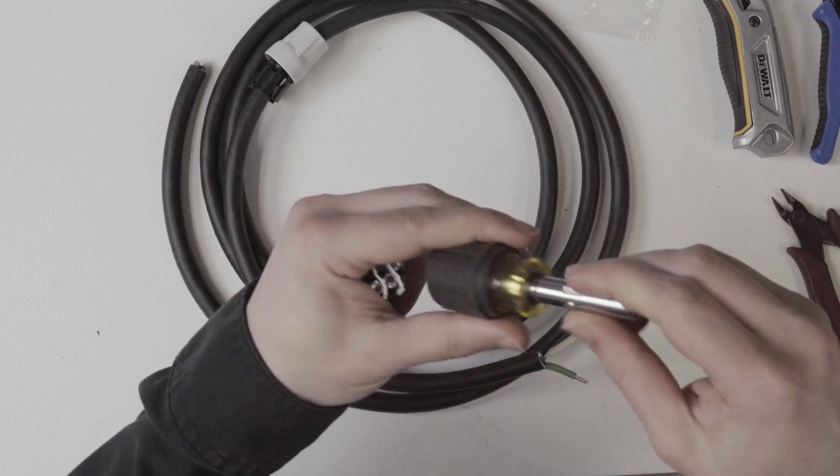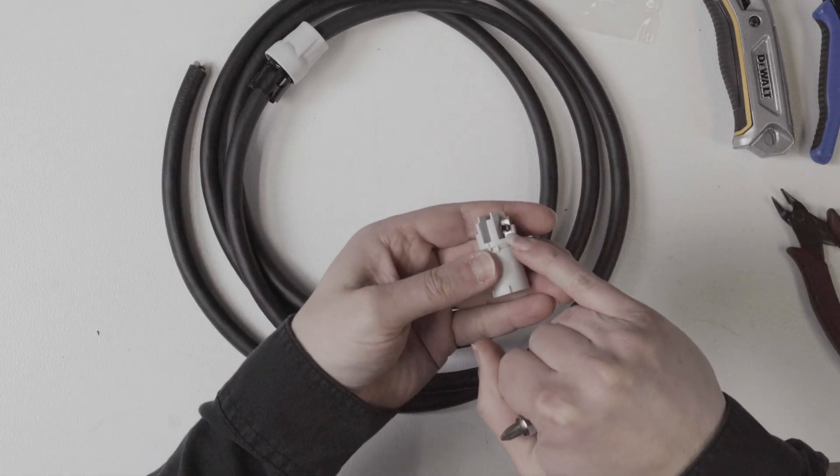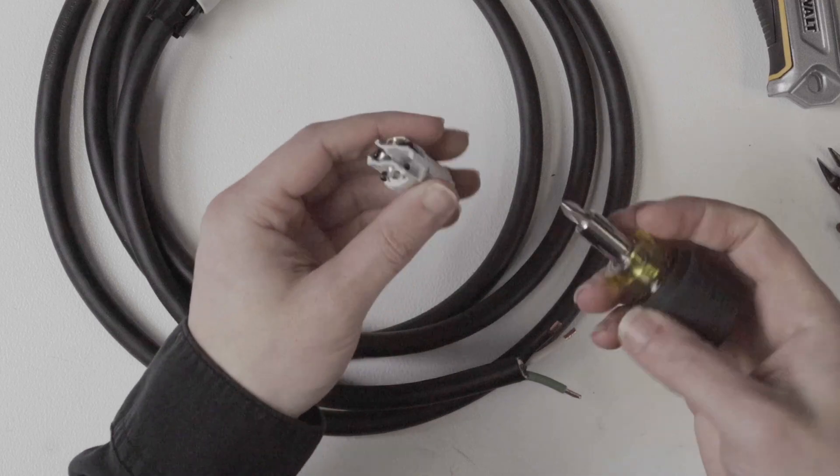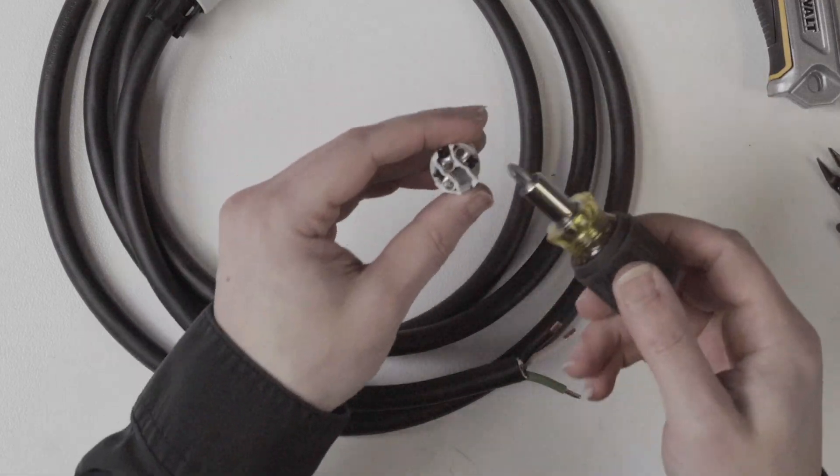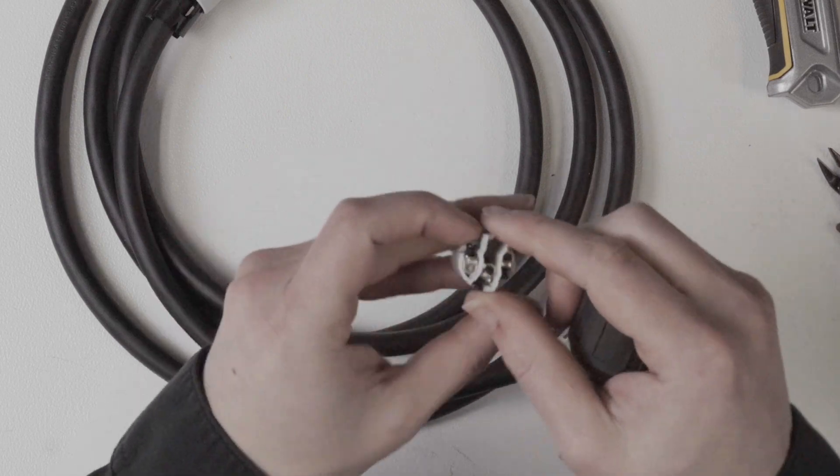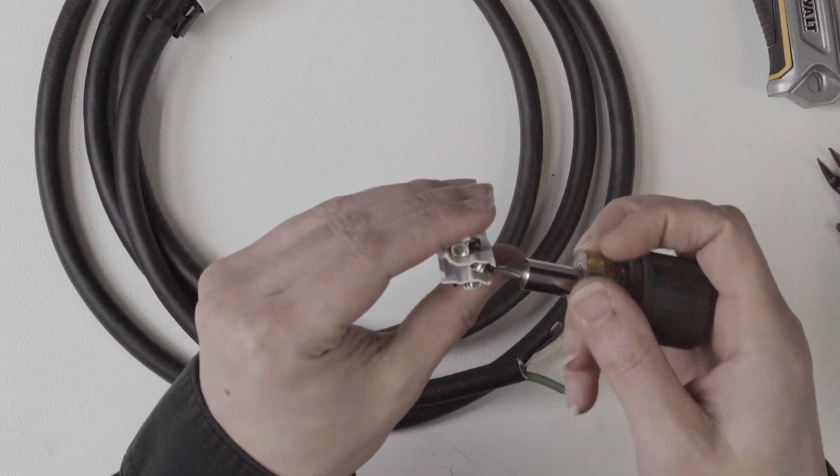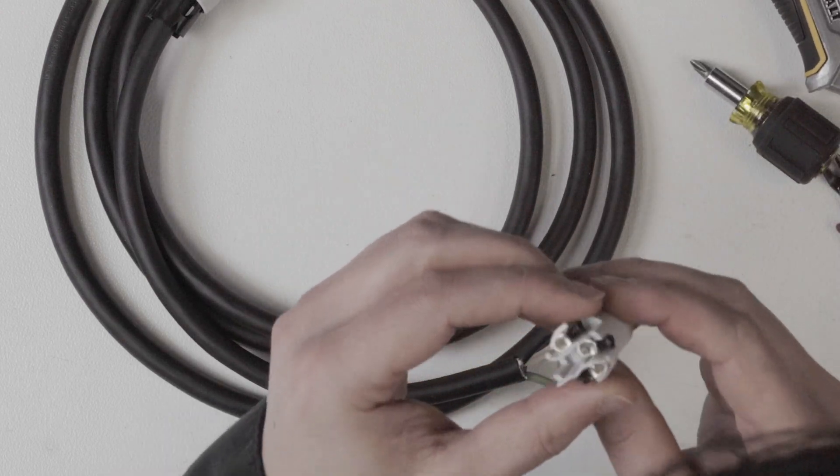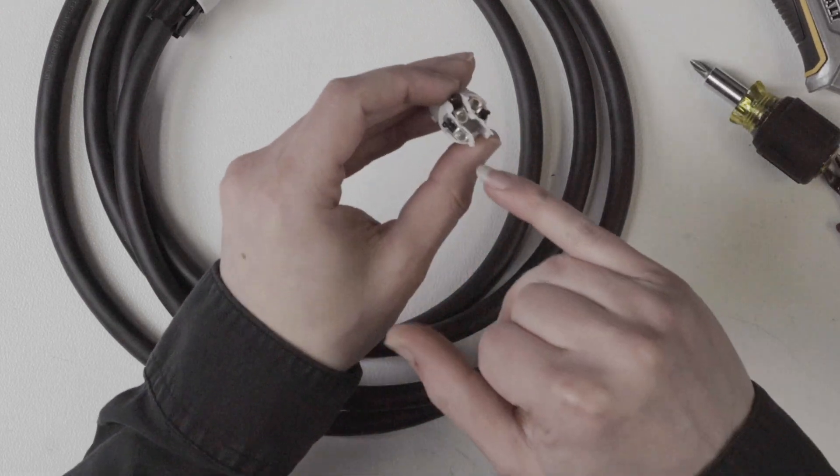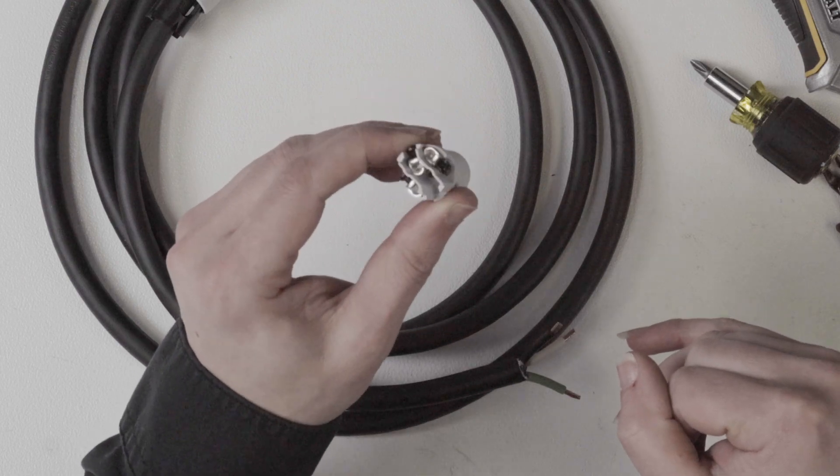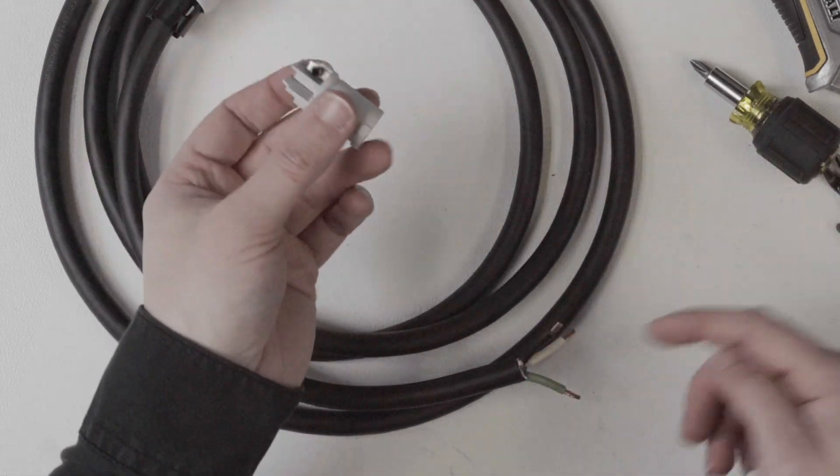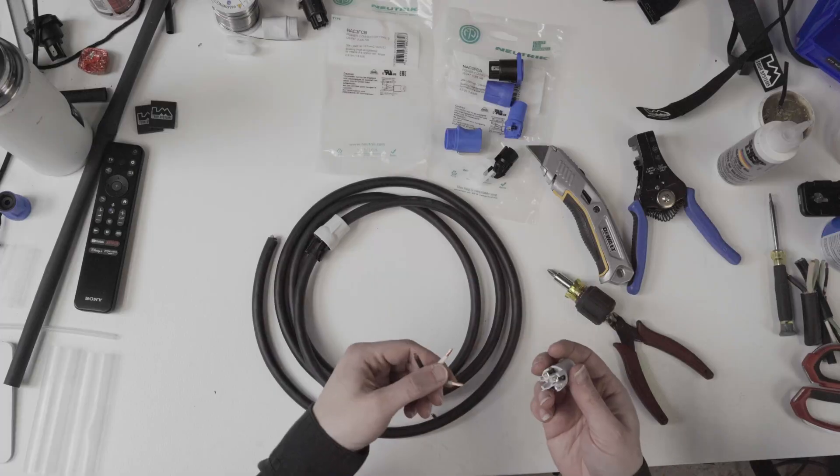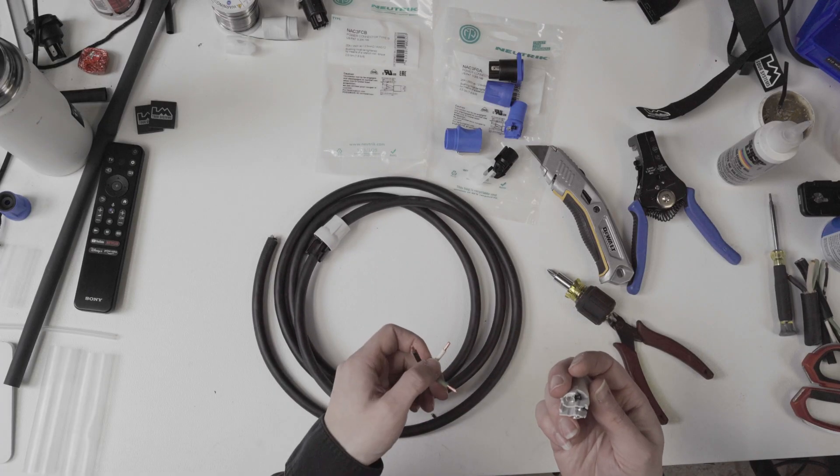Okay and then I just like to give these a little twist. So here's the tricky part about building a powerCON. The screws in here are a Pozidriv. They look like Phillips they're not. I'm using a Phillips head screwdriver. I should be using a posi but alas that's where we're at today. So I just like to open these up. On each of these the conductors here are labeled L ground and N. L is your hotline your black wire, N is your neutral your white wire and G or the earth symbol is ground your green wire.